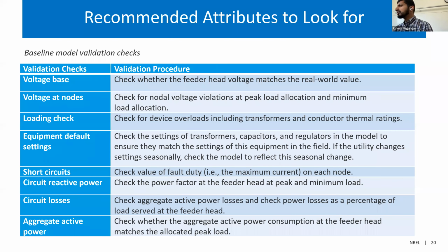Another parameter which is less talked about but very important is to check the power factor at the feeder head at peak and minimum loads. Power factor is a ratio of active power to apparent power. You want to make sure there is the right amount of reactive power being consumed by all the aggregate loads. If you see very out of range values, 0.7 power factor or a very leading power factor, that means something is wrong in your load allocation and load values. Also make sure you check the aggregate power losses at the feeder head and overall feeder, and understand what percentage of load is served and what percentage of that is power loss.